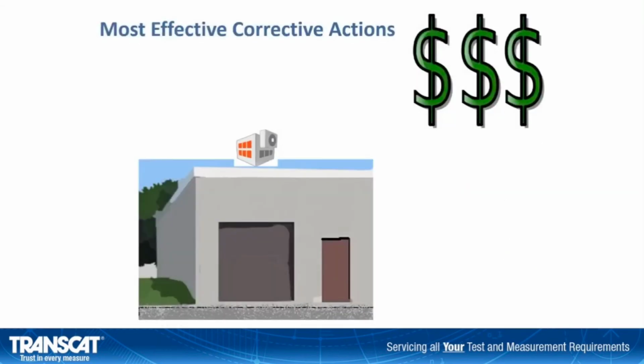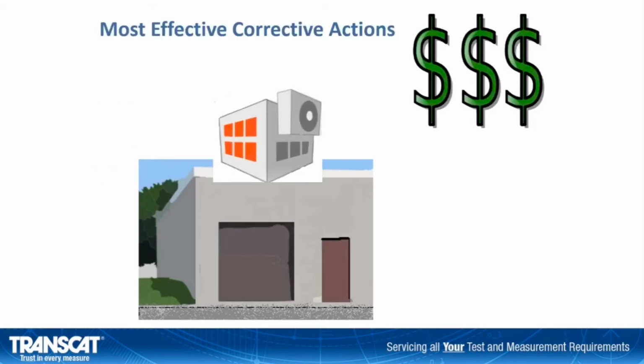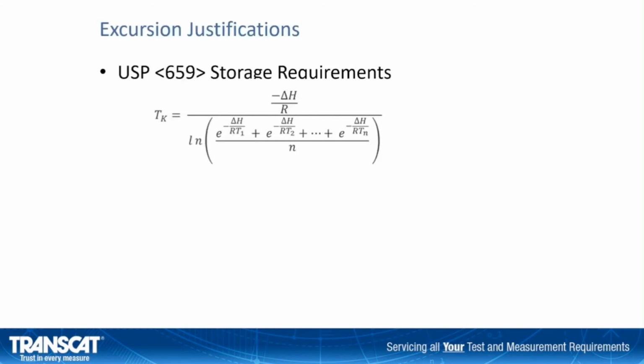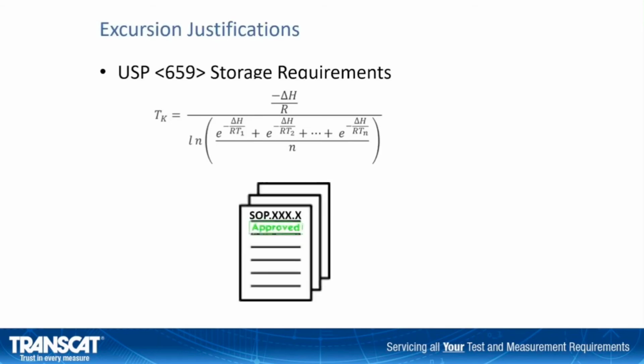The most effective corrective actions also come with the highest cost. Some options could include installing a higher rated insulation in adjacent walls and ceilings of the storage area and upgrading the HVAC system of the building to one that can adequately maintain the required temperature. Excursions can be justified via other means. United States Pharmacopoeia allows excursions if the calculated mean kinetic temperature, also known as MKT, does not exceed 25 degrees Celsius. Other justifications are also valid, such as following an internally approved quality document that details excursion responses, or having a scientifically valid justification of no impact.